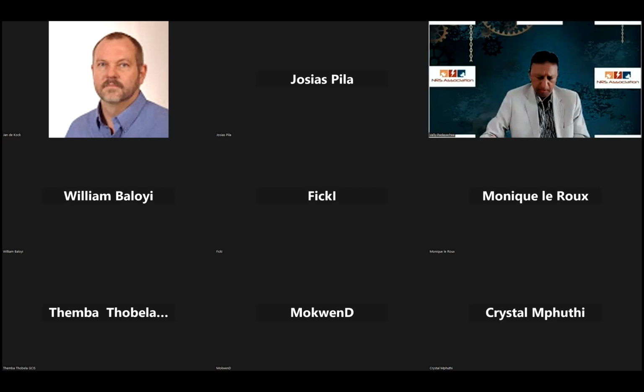Just to add to Isabel's point about UFLS and Black Start, there's a requirement in terms of the grid code, also NRS 048 Part 9, that those initiatives are done regularly. As an NRS association, especially in the last year, we've been in very close contact with the system operator and national control, so we are very comfortable that those actions are taking place, and the risk of a blackout or grid collapse because of those is absolutely minimized.